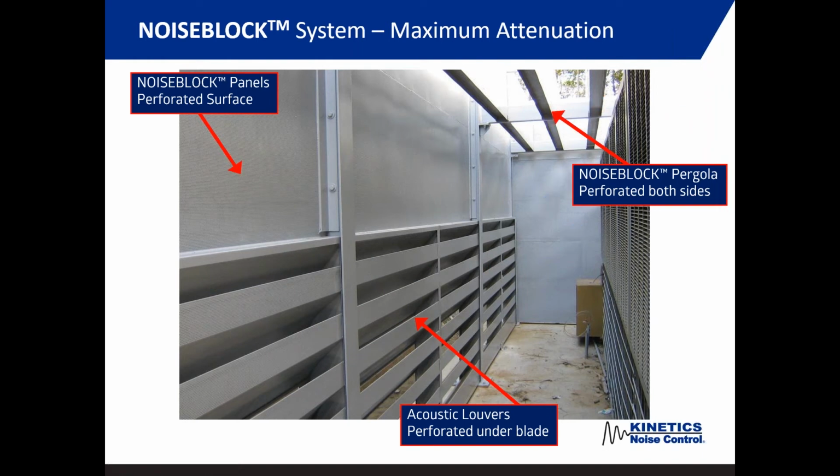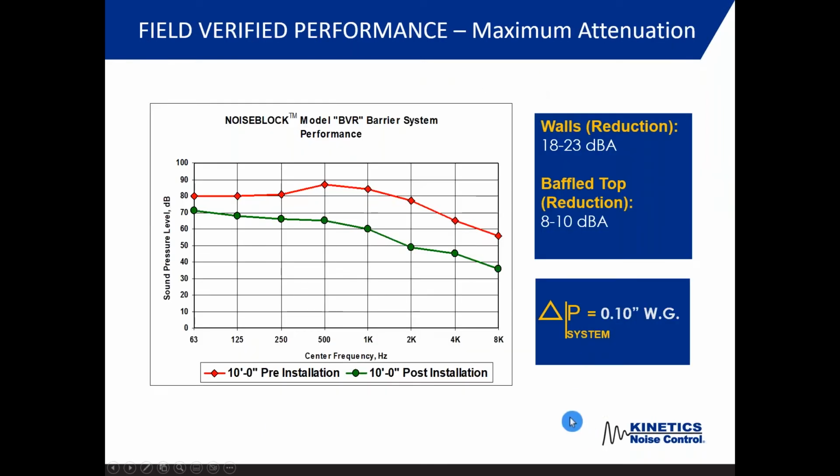Similar to a pergola you might have on your back patio, hanging wind chimes and different things. So that's what we call it, a pergola. Now, these panels are 4-inch thick, and they're perforated both sides, so they kind of work as silencer baffles. If you look at this maximum attenuation system, if you're standing outside the walls of the system at 10 feet, we measured anywhere between 18 to 23 dBA reduction. Remembering that 10 dBA reduction is going to be perceived by the average human as sounding half as loud.